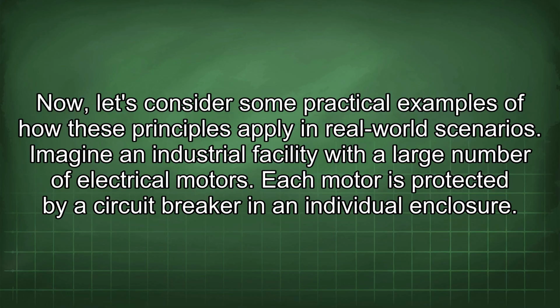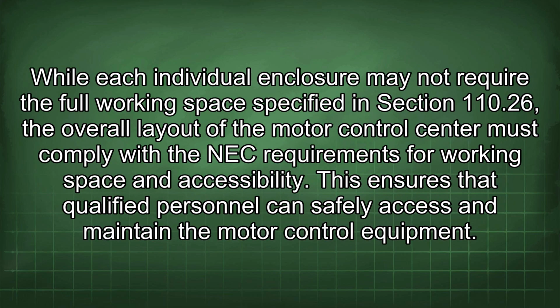Now let's consider some practical examples of how these principles apply in real-world scenarios. Imagine an industrial facility with a large number of electrical motors. Each motor is protected by a circuit breaker in an individual enclosure. While each individual enclosure may not require the full working space specified in Section 110.26, the overall layout of the motor control center must comply with the NEC requirements for working space and accessibility.